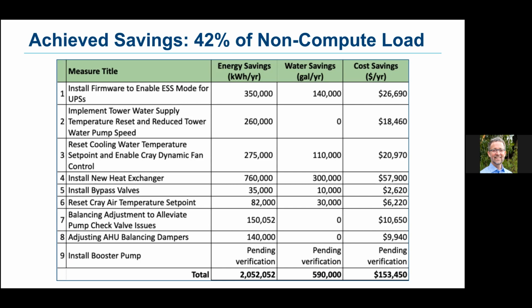The first is an example of a hardware-based measure, enabling energy saving mode for UPS. A lot of what we're doing in many cases is looking at the sequence during different outside air conditions and optimizing that sequence so the appropriate and lowest energy consuming portion of the system takes the lead. At item 4, that's a retrofit, installing a new heat exchanger and generating pressure drop. And then we've also crept into the compute side a bit, doing some modulation of the Cray fans as part of the cooling system in relation to the cooling towers. So a little over 2 million kilowatt hours a year of savings and 500,000 gallons of water savings.